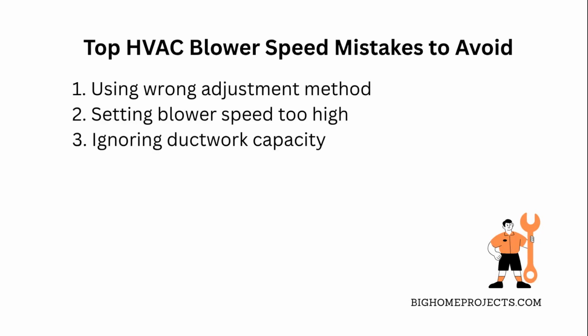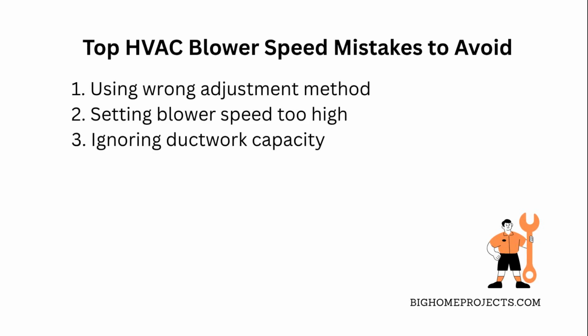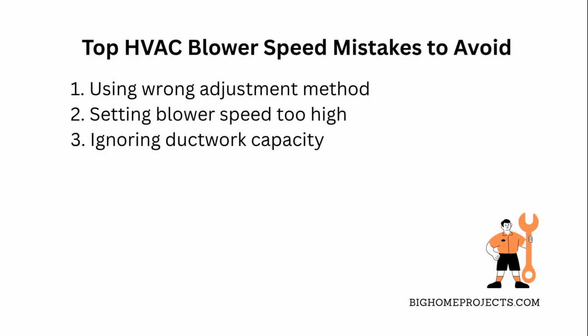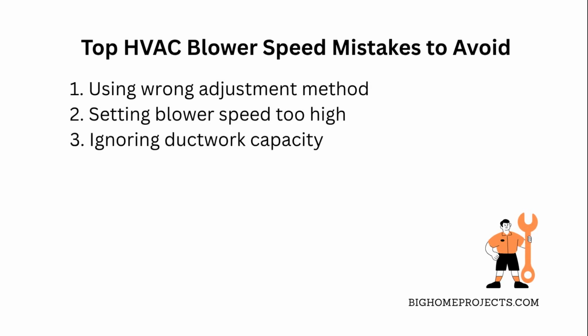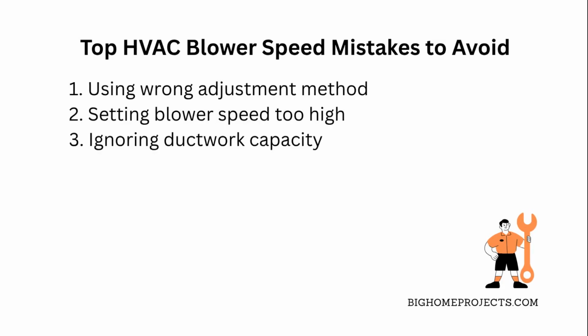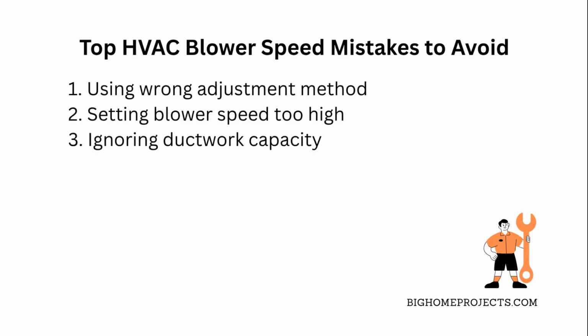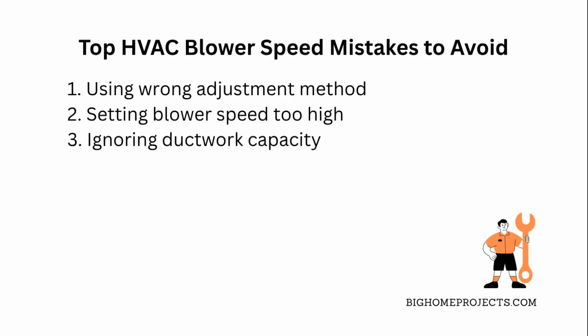One of the biggest mistakes folks make when adjusting HVAC blower speed CFM is guessing without any real data, just cranking it up or down and hoping for the best. That usually leads to wasted energy and more discomfort. The fix? Use a digital thermometer and humidity gauge to get actual readings before making changes.